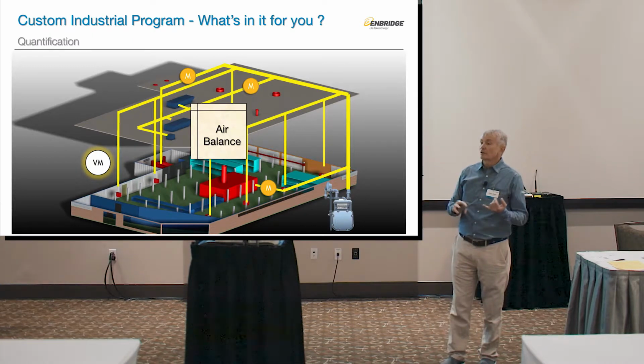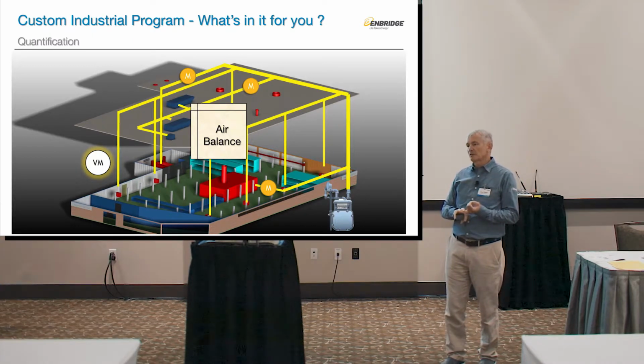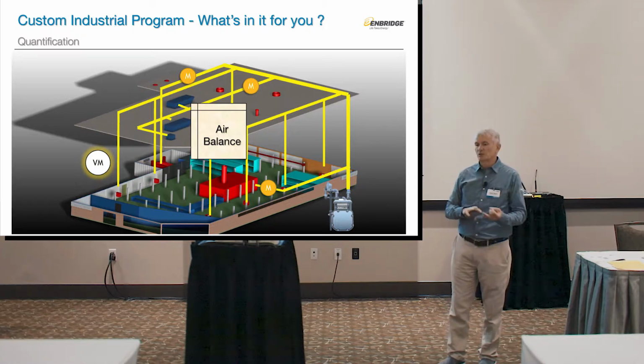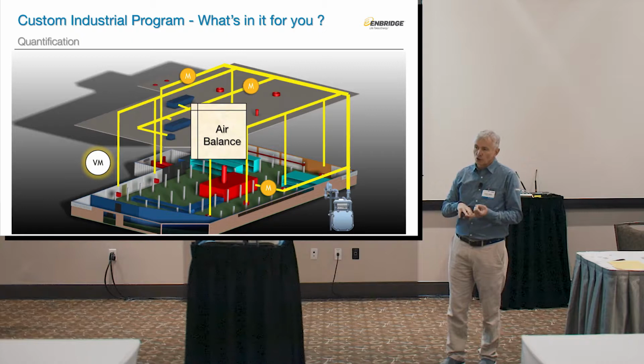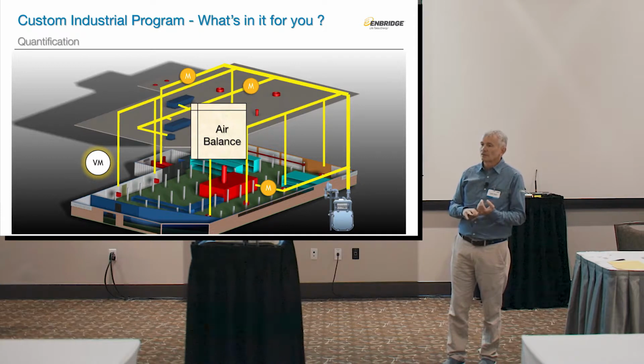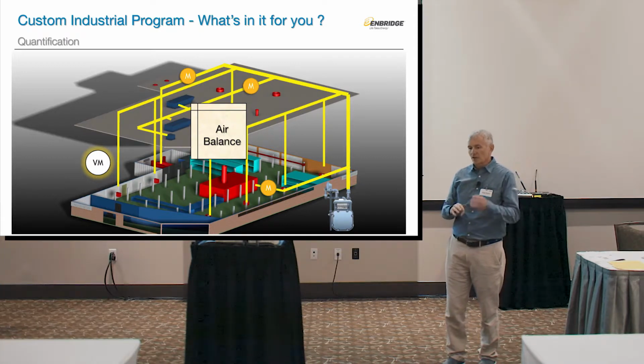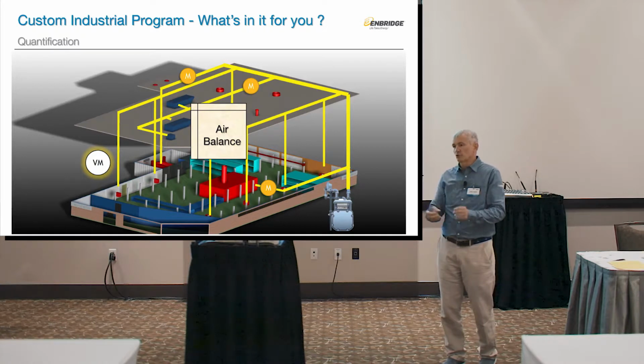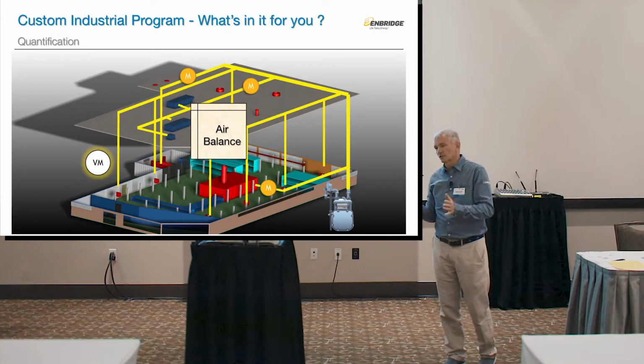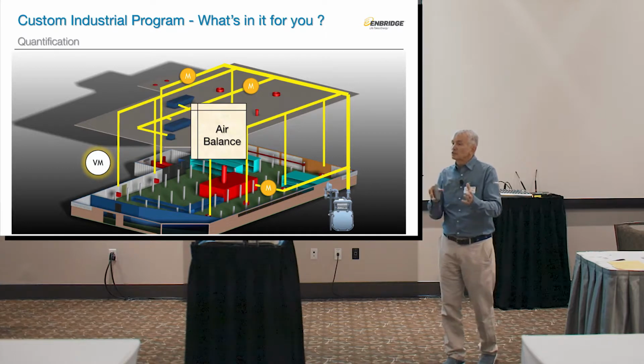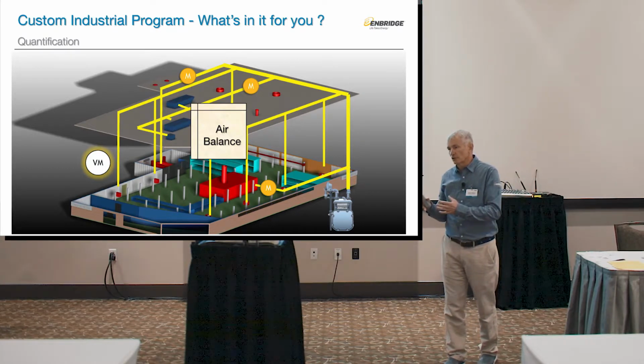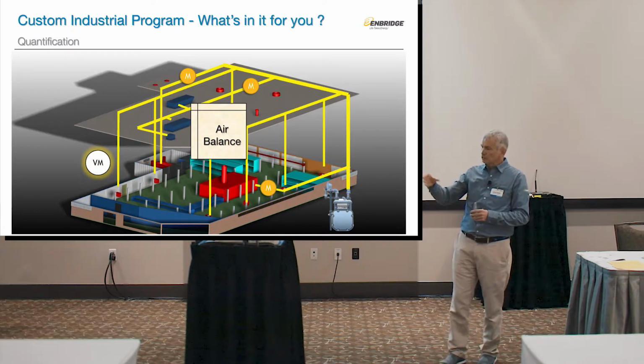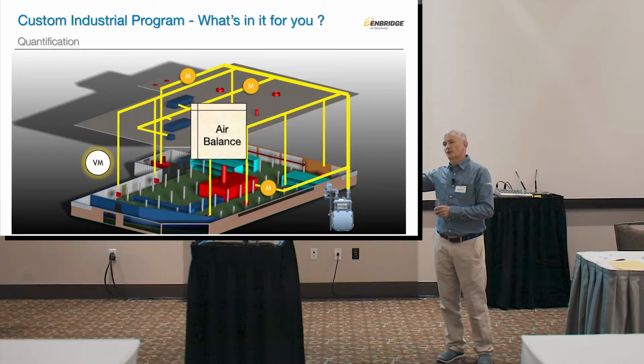Steam meters are usually relatively expensive to install, and the problem with steam meters, from my previous experience, is they go out of calibration often, so you have to recalibrate them. We have Akil on our technical staff, who is more than capable. If he has natural gas usage and water usage, he can predict exactly what your boiler is going to produce. So it depends on how important that piece of information is. Some people will use steam consumption where they charge other departments for usage, for example. In that case, you need steam consumption anyway. You might as well use that rather than metering other inputs.